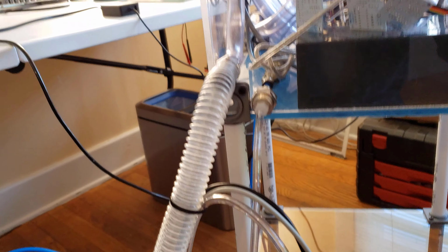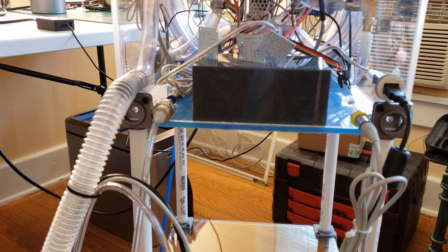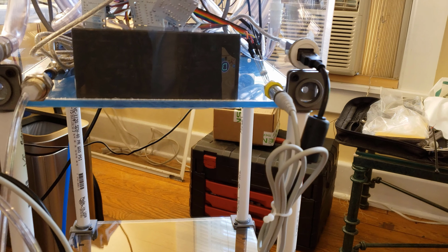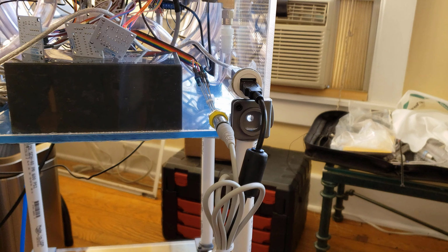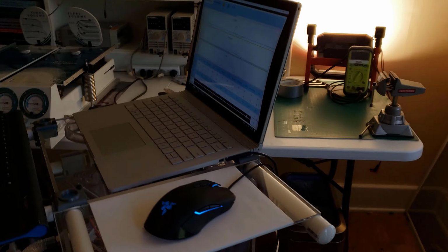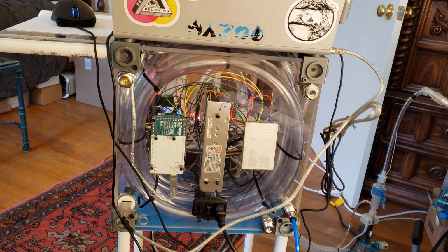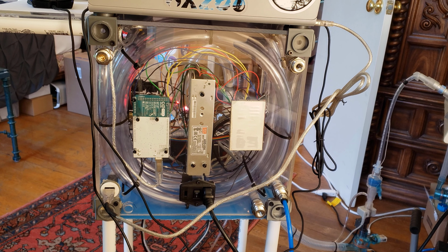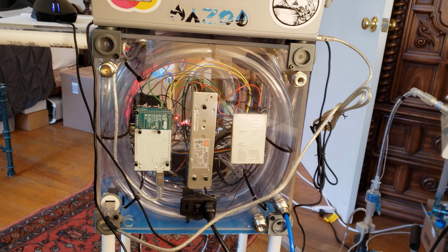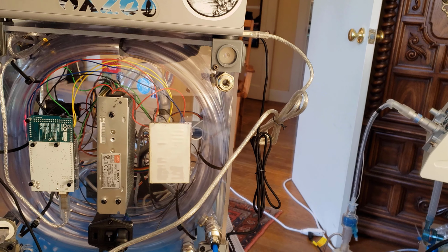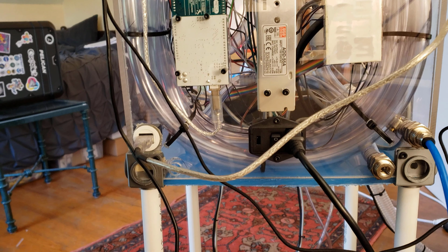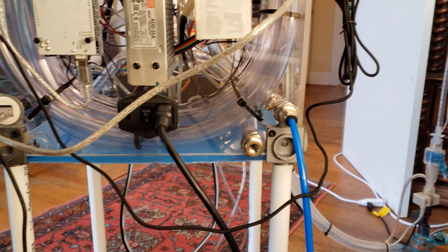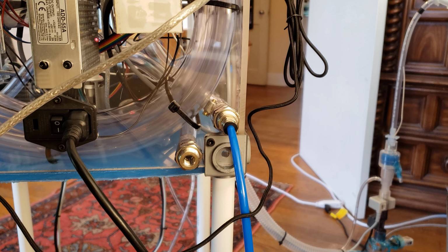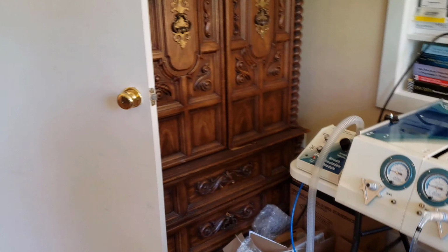Looking straight at the ports, we have from the left to the right the patient circuit hose, the pressure line, ETCO2 sensor connection, and the flow rate connection. And then on the back, we have from the left to the right a no connect port, and then we have the exhaust. Here is the connection for the Arduino to the computer, and here is the AC voltage connection, and then the input oxygen and the input air. Both of those are ICU 50 psi standard air inlets.